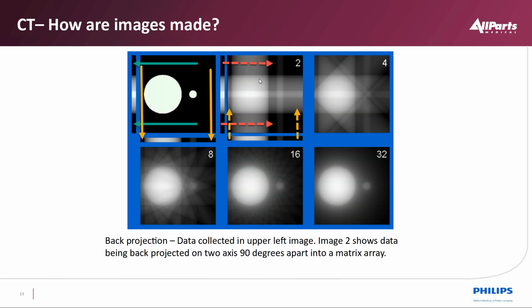So what we have in image number 2 is if we take and push that data back through a grid, originally the grid size in a math grid, within the computer, we would push the data back. This is called back projection. As we push more and more data back from different angles, we start to represent more of what was scanned. So this is known as back projection in the process of CT. As we approach more and more angles, we more closely represent what we saw. So in the image here, we basically have a lot of ghosting and stuff.